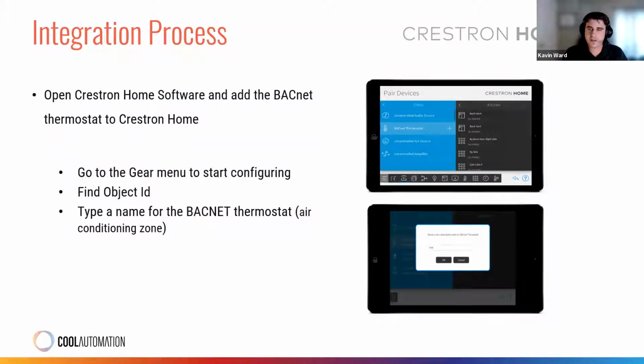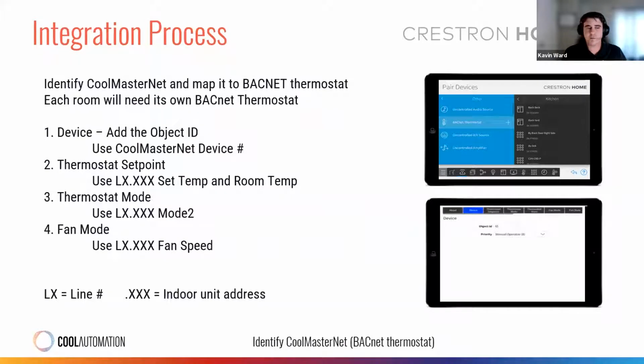From your Crestron Home side, once you have each of your zones set up, you'll want to hit the gear to start configuring. Find the object ID from Yabe, in this case 64. But you also want to click BACnet Thermostat and add that BACnet Thermostat to your zone. In our example, it's the kitchen. So now we're adding the controller to that zone. And then from here, there's a 4-step process to complete the mapping. So we're going to add the device. We're going to configure the thermostat set points, the thermostat mode, and the fan mode.